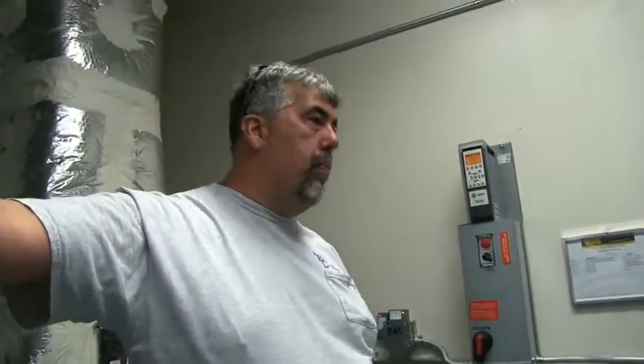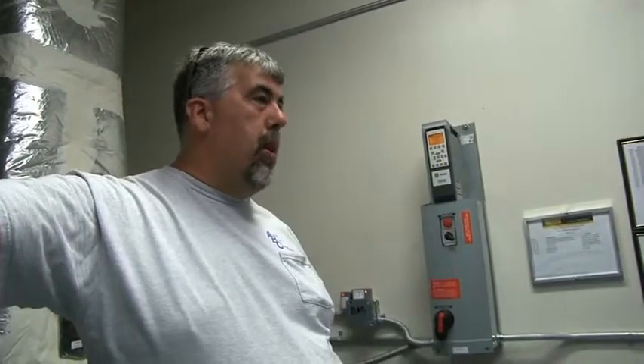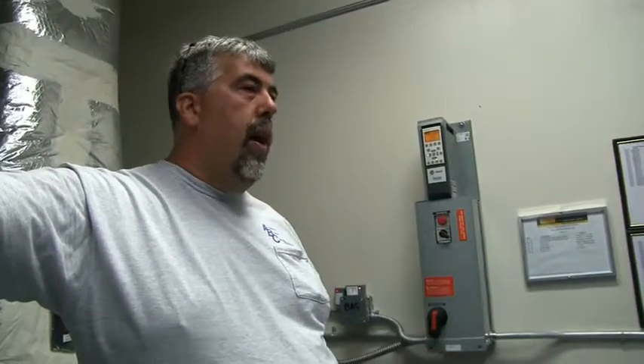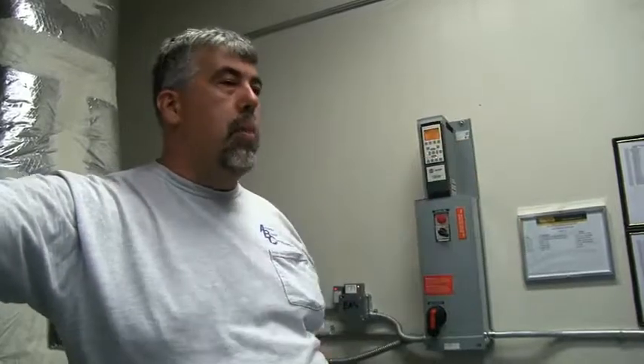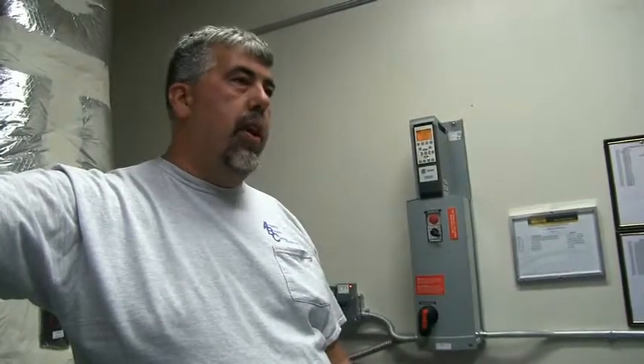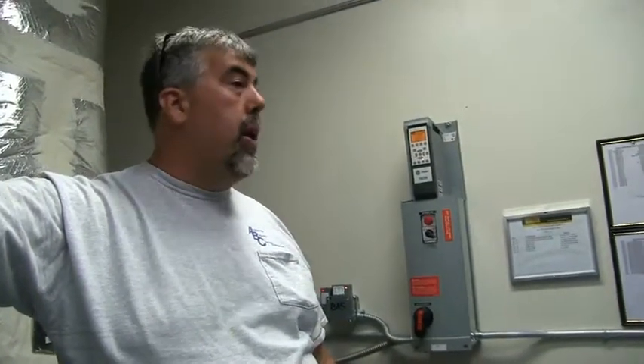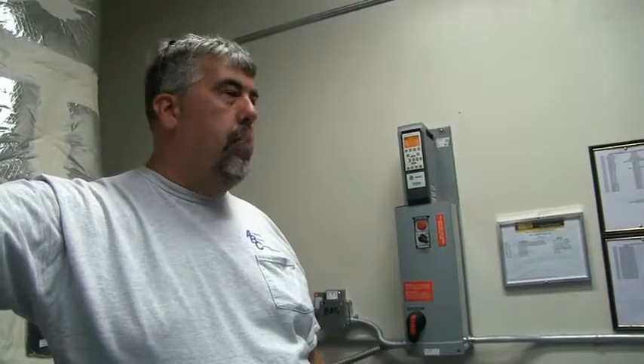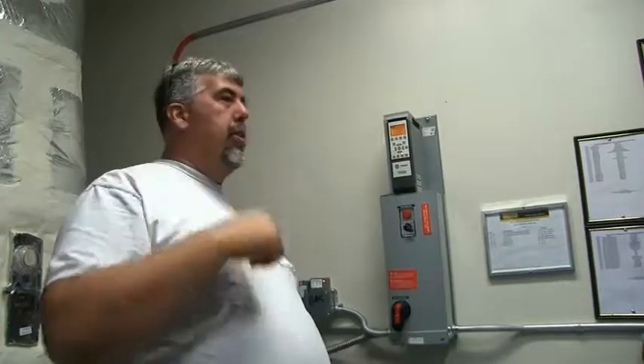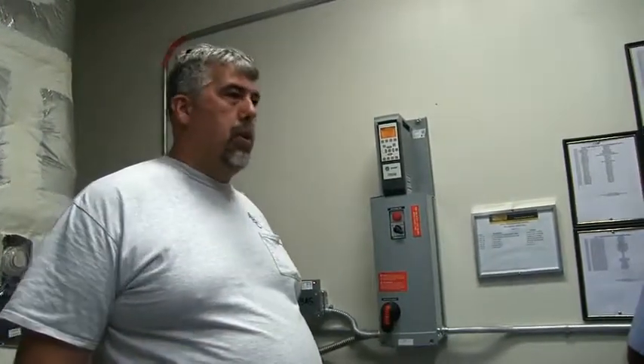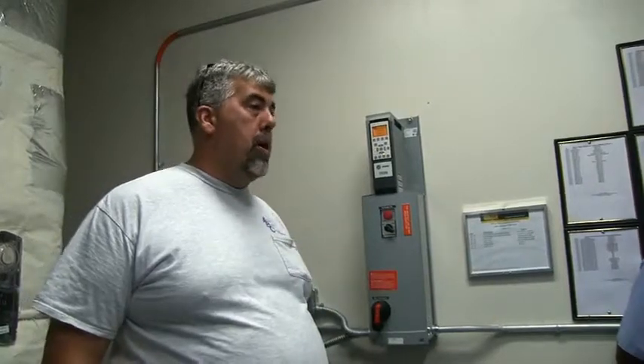So your static will do the same. So that way you're drying out your building, and the heaters out there will maintain space temperature. That's all they do. The heaters just come on to maintain space temperature. They're not part of a sequence for dehumidification. Okay. So I just want to throw that out there. So what do they do currently? They just work the way they're supposed to work. Right. Whatever their heating set point is, they're going to maintain.